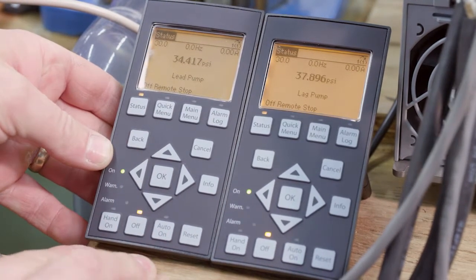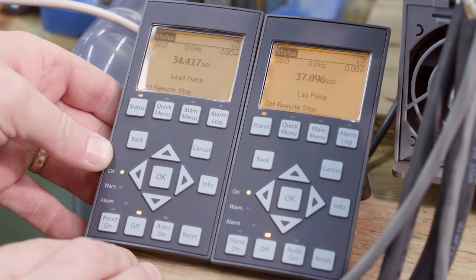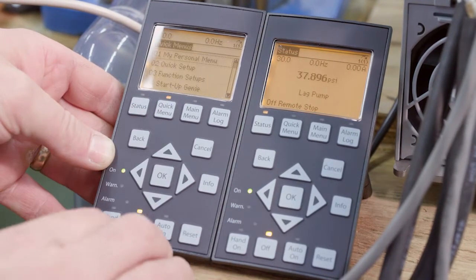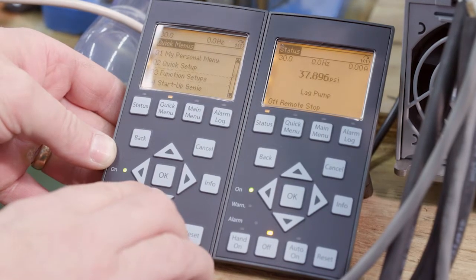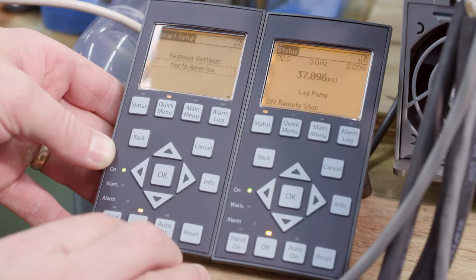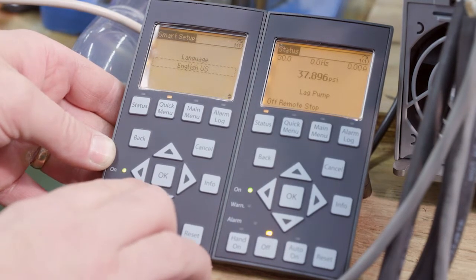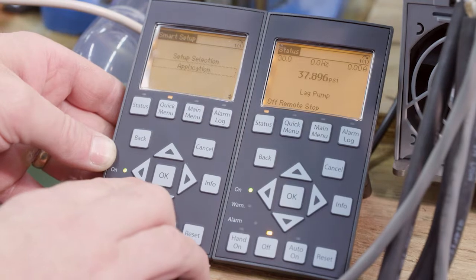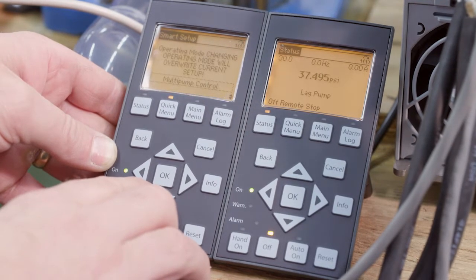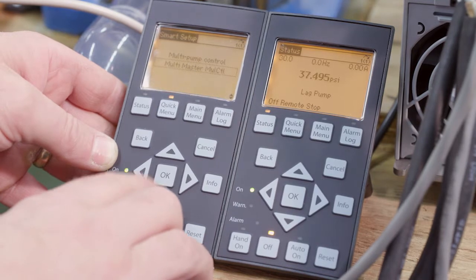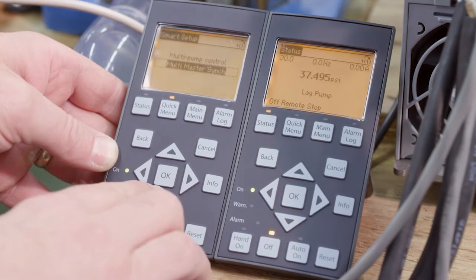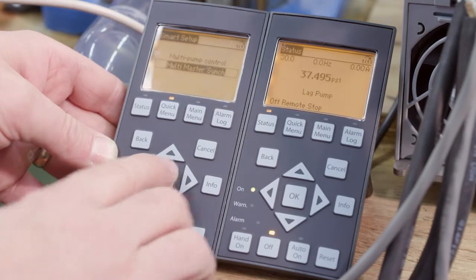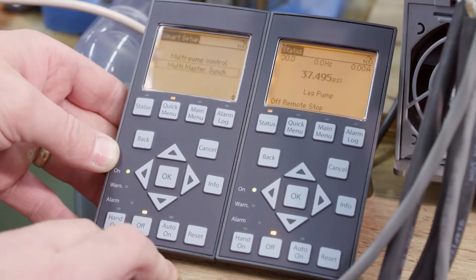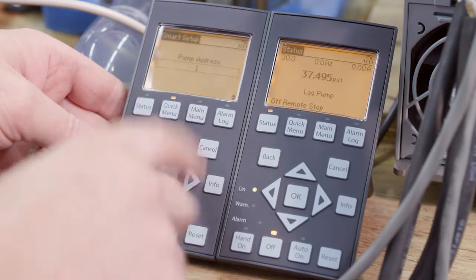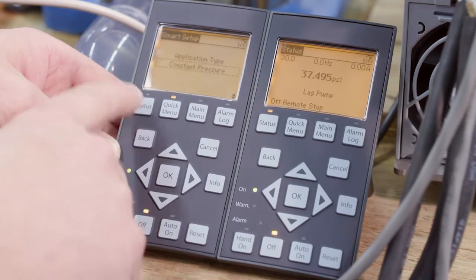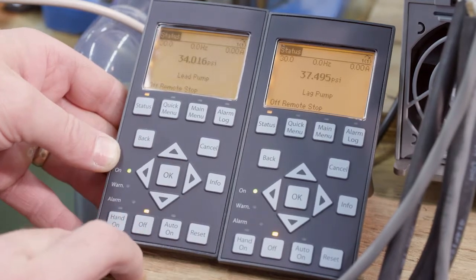So in order to get back into the Genie or Smart Setup, one easy way is go to Quick Menu and go to Startup Genie. So you can always go back to the Startup Genie. So multi-pump control, and we want to change this to Synchronous. So multi-master Synchronous. So I'm going to make that one change here and save it. Pump address 1, double check that. Okay, so now I'm going to go back.